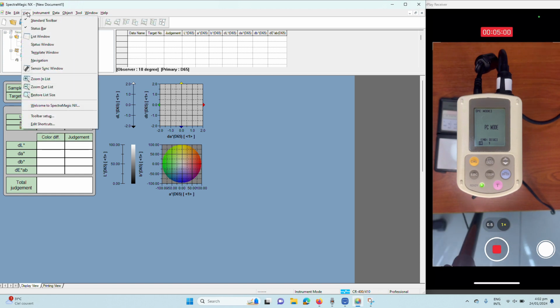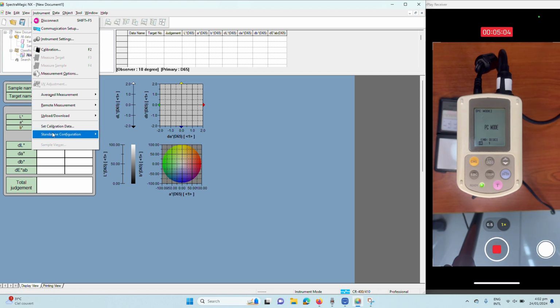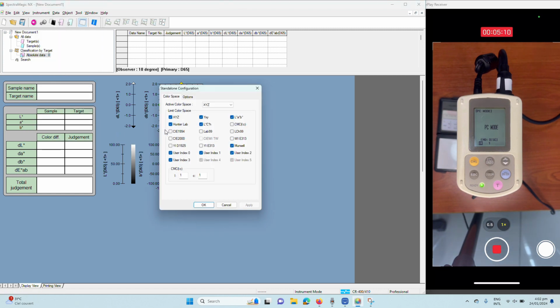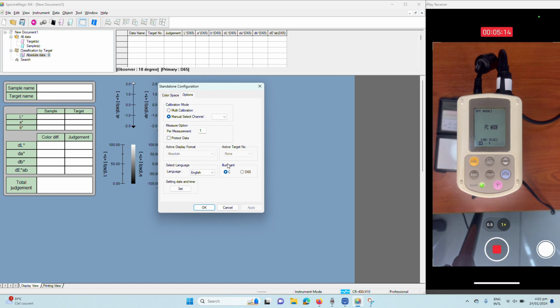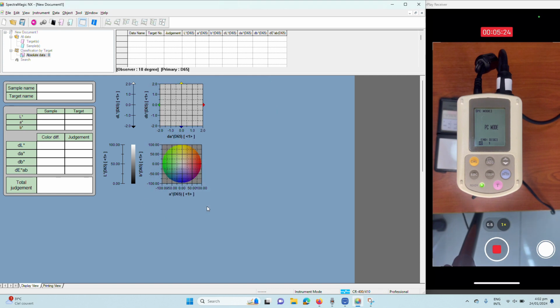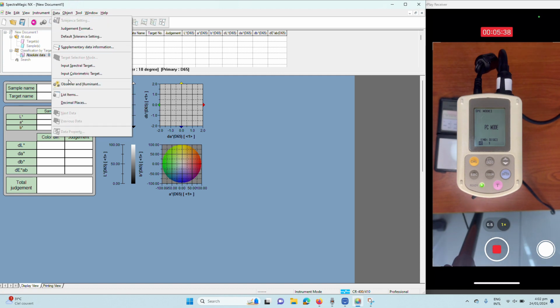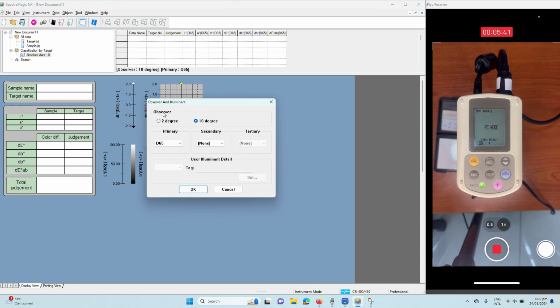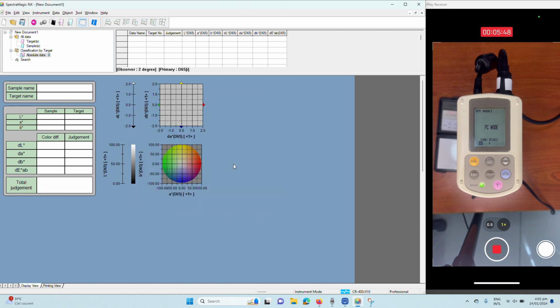Now, let's say you want to change that. You don't want to use C because your standard follows D65. Go back to standalone configuration and option, change the illuminant to D65, apply. So now your equipment is D65 and the measurements in your software are D65. Of course, the next thing to do is, because on my side you can see that the observer is 10 degree, I can tell you this will not work because I cannot take measurements using this. So what do we do? Go to observer and illuminant, change it to 2 degrees. There we go. Okay, yes, I'm sure.